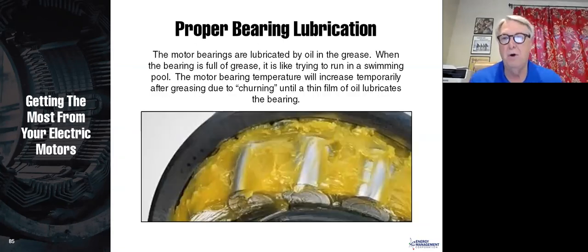Now, look at that motor. Grease is a holder. Grease does not lubricate bearings. Grease simply holds the oil so that the oil can lubricate the bearings. If you have too much grease in there like that, and this is what it may look like after you grease it, then it's going to be like swimming or like trying to walk in a swimming pool. You get this churning, and that bearing is going to get very hot. And so that's why it's very important to open that drain plug and allow that grease to come out.